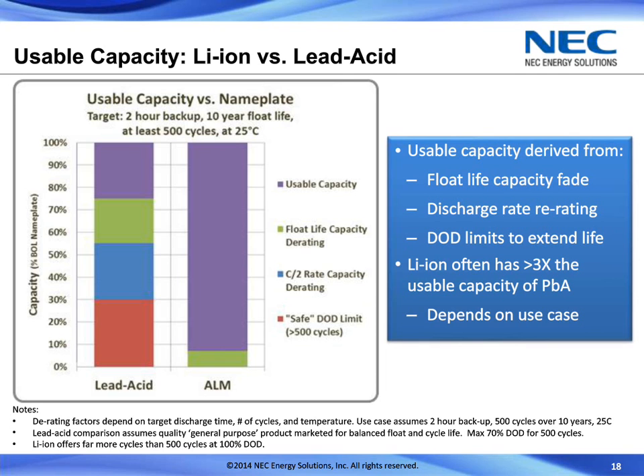application. The target application would be 2 hours of backup, working over 10 years, so there's some degradation associated with the float life over that 10-year period. Over that 10 years, we're probably going to have some instances of use. So say we're going to cycle the battery 500 times over 10 years, which is not a whole lot, and we're able to maintain that battery at, say, 25 degrees C.